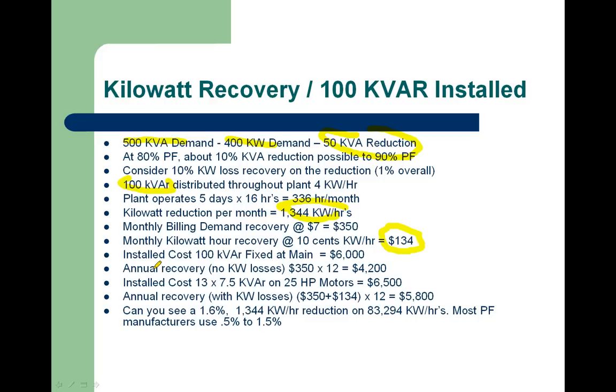And if we were to look at an annual recovery of the demand charges, we would be looking at an annual reduction of about $4,200, which would be a very, very good payback, of course, on 100 kVAR. Now, if we took 13 7.5 kVAR capacitors and installed them on 13 25 horsepower motors that were a minimum of 250 feet from the main switchboard, and generally on smaller cables, so that they were at least 2/3 loaded, we could see potentially the I²R loss recovery, as I said, of $134 a month.